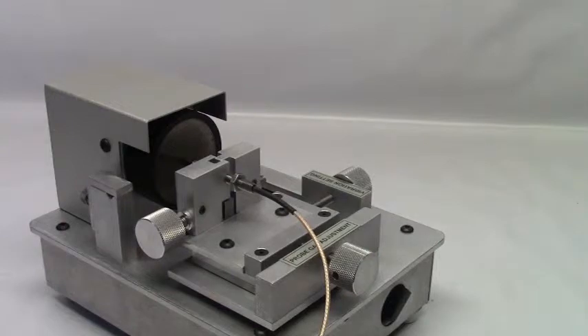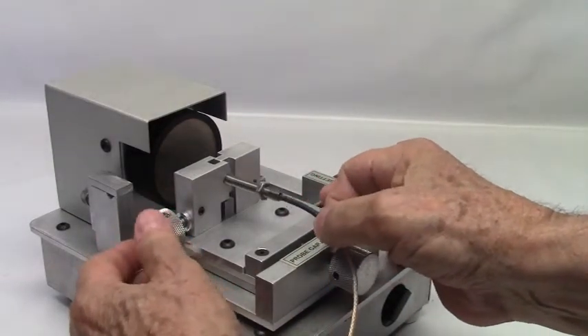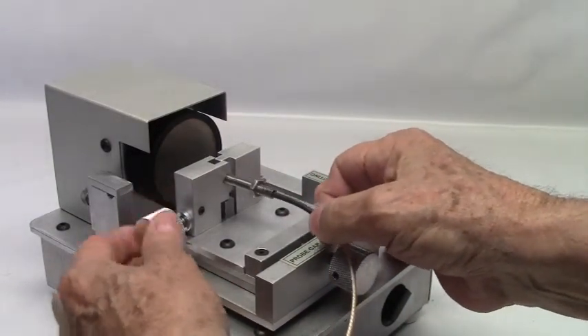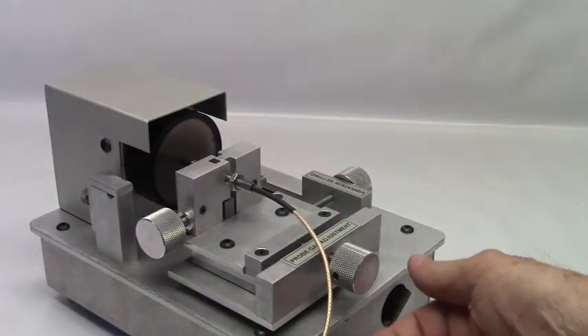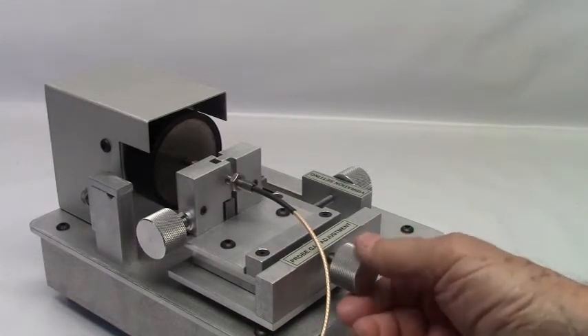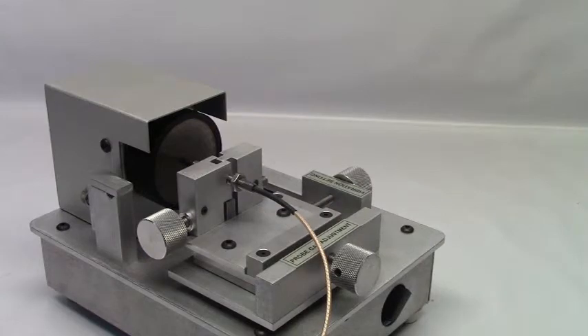Four, adjustable probe grippers that will hold any probe from 5 millimeter up to 19 millimeter. The grippers can adjust out or in, place that against the surface of the wobble plate, move this back one full revolution, that equals 50 thousandths at the point of the probe.